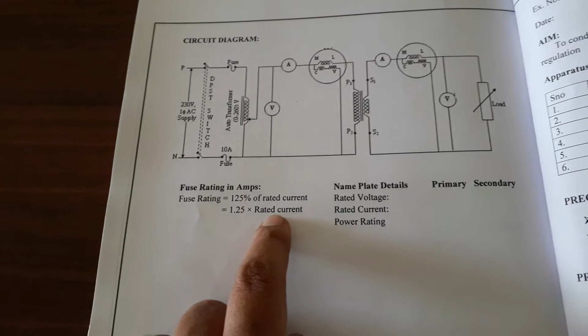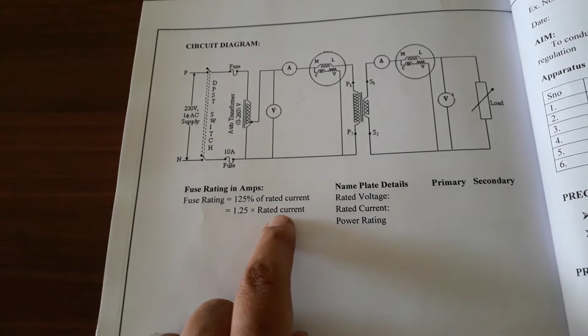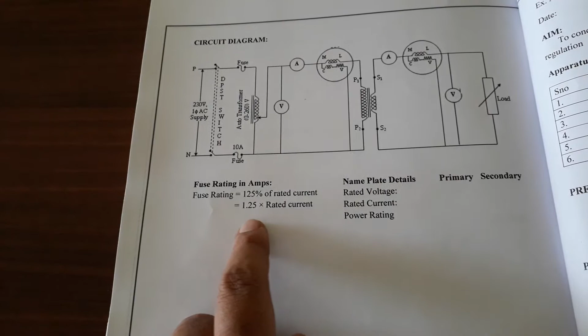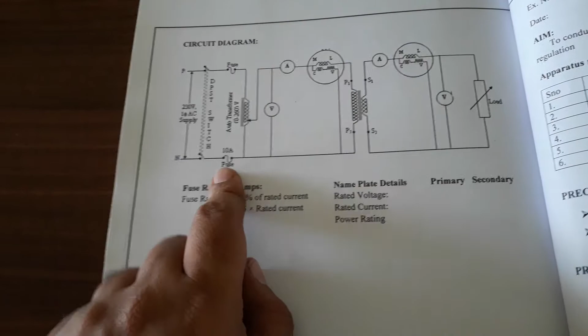That means 1.25 times the rated current. So what is the rated current here? You have to refer to your nameplate details. Here it is mentioned as 4.3. So 1.25 into 4.3 amperes. What is the fuse rating? You have to fix it at the nearest integer of the highest value. So for example, let me take it here as 10 amperes.